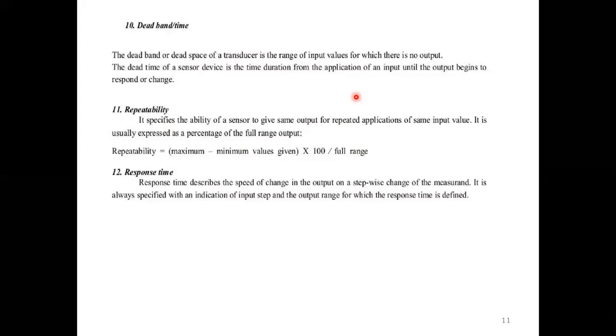Okay. So response time. Response time describes the speed of change in the output on a step change of the measurement. It is always specified with an indication of the input step and the output range for which the response time is defined. That is response time.